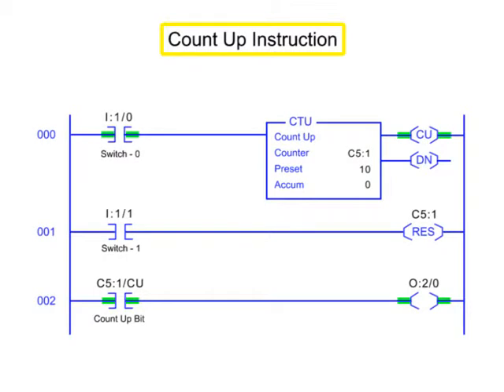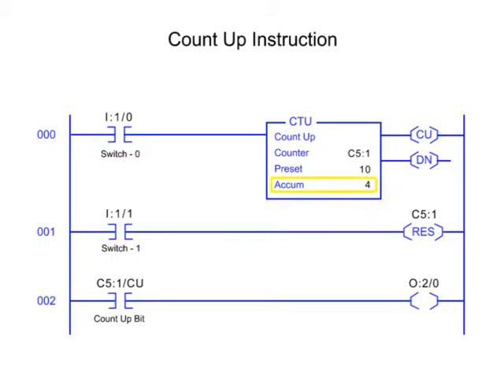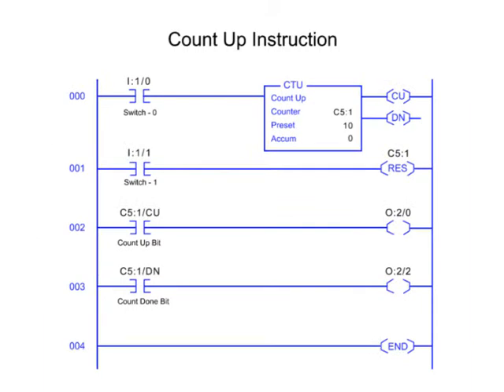Count-up and Count-down instructions are used to count rung transitions. The Count-up instruction, or CTU, is used to count false to true rung transitions. When rung conditions for a CTU instruction have made a false to true transition, the Count-up Enable bit is energized, and the accumulated value is incremented by one count.